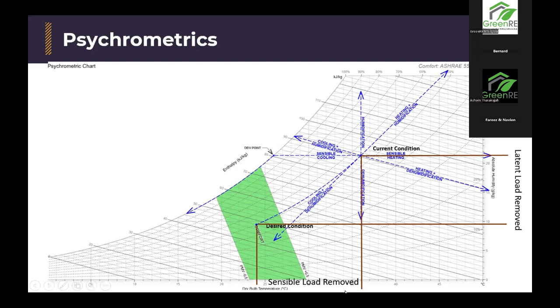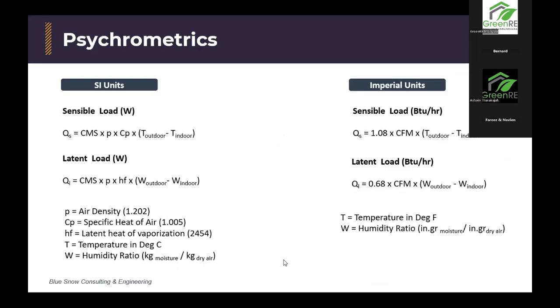You'll draw a line straight down. You'll check the dry bulb temperature here, dry bulb temperature here. You'll plug it into a separate formula, and you will know your sensible load. So now you know exactly, for my space, what is the ratio of humidity removal to direct cooling that I need. So these are the formulas. I've given them in two formats, the imperial units and the SI units. CMS is all the flow. It is not just important that you have a coil running, you need to know how much air is flowing through it. A combination of those two is how much heat you're trying to remove from the space.